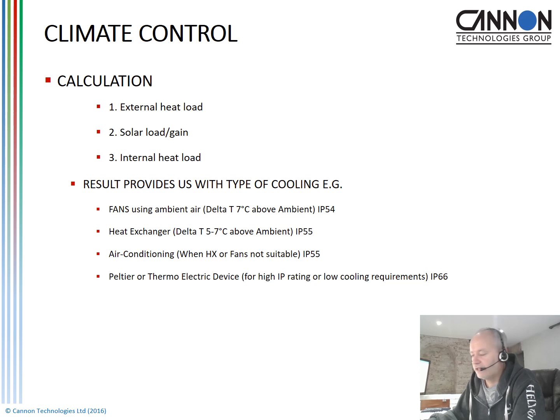So, for example, if the external ambient temperature is 30 degrees and we can operate the equipment inside at 37 degrees, then we know we can use active fan forced air cooling. Other options are heat exchangers, if we need to increase the IP rating or we need lower delta T figures of within 5 to 7 degrees. Air conditioners are useful if the delta T is much lower than 5 degrees for ambient air cooling. For example, if the equipment needs to operate at 30 degrees and the ambient temperature is going to be 30 degrees, we'd need an air conditioning unit, because we would not be able to use that ambient 30 degrees to cool that equipment.